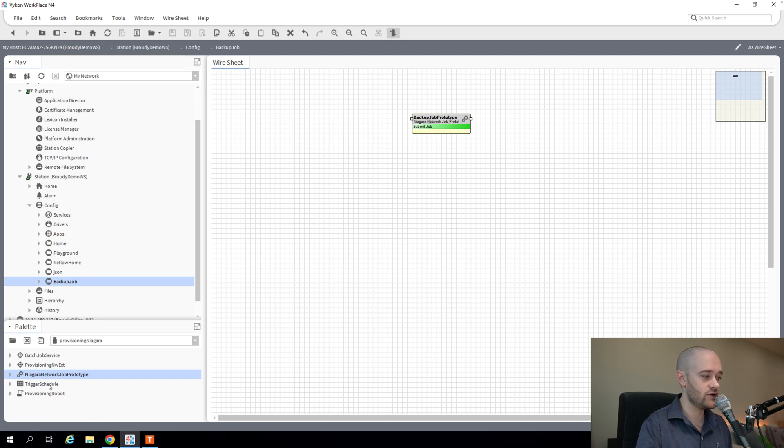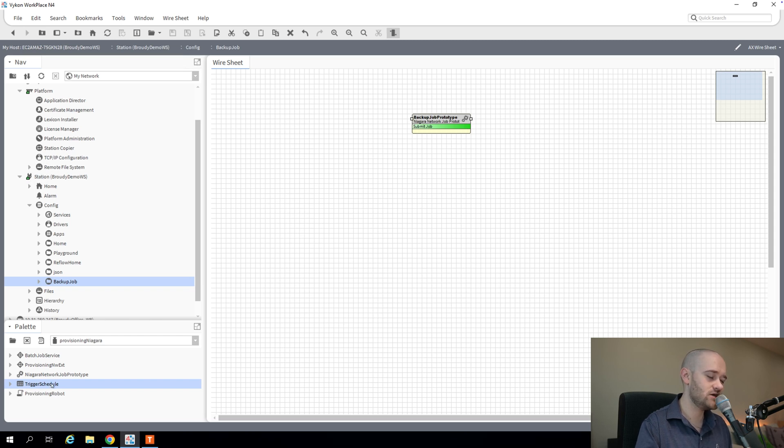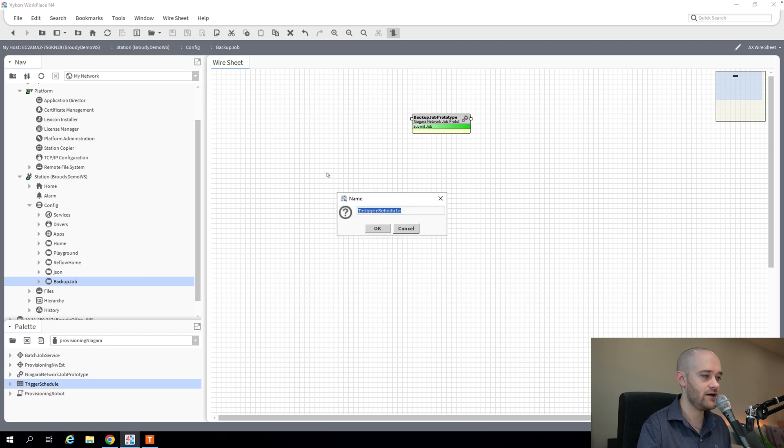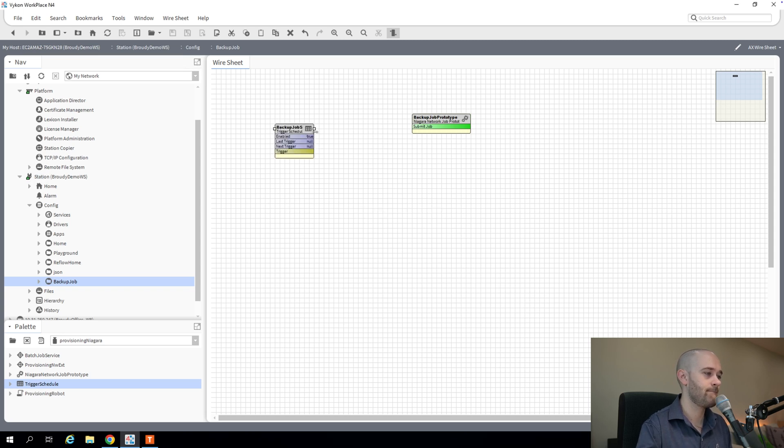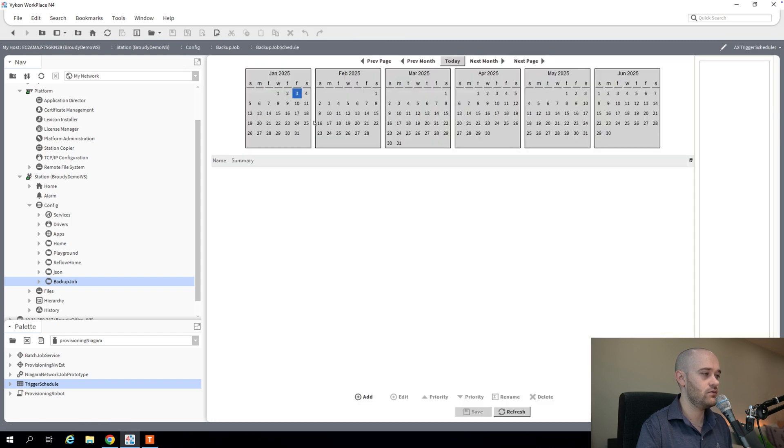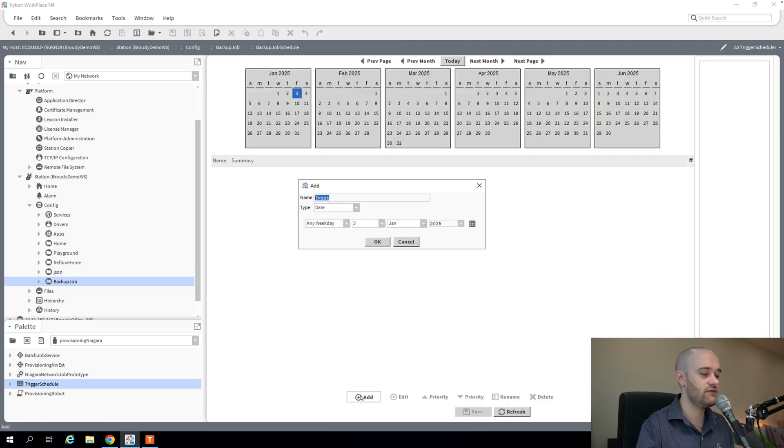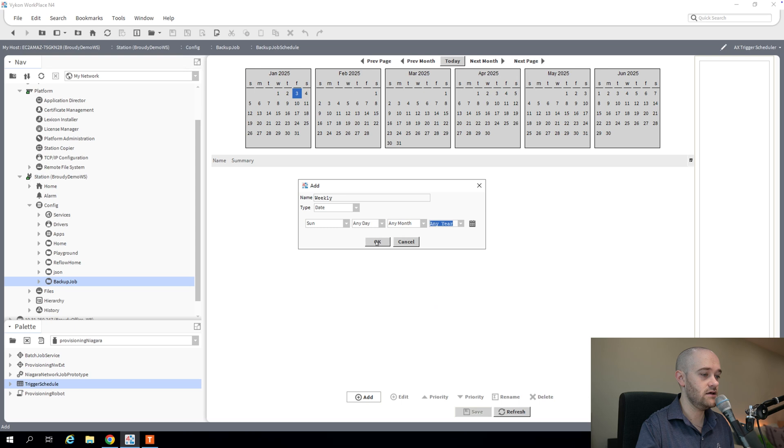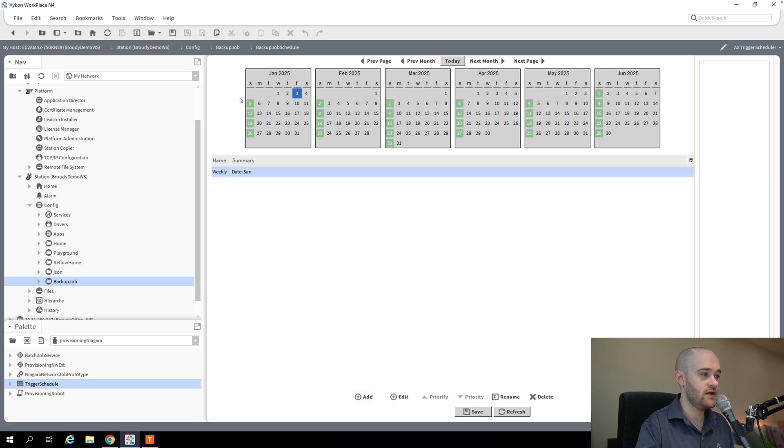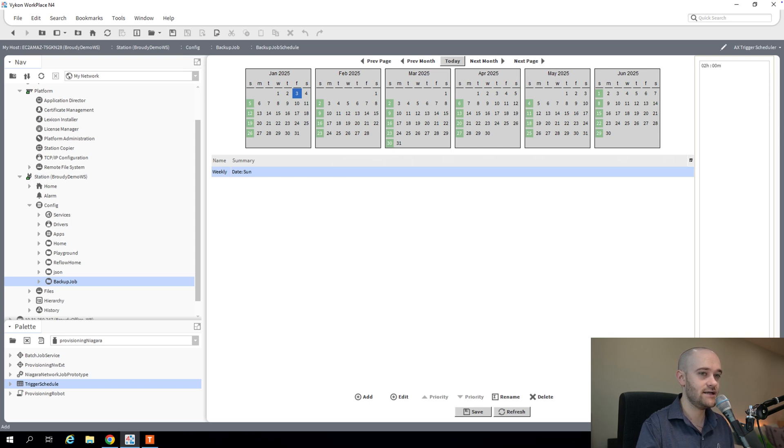And the way that we're going to do that is we're going to pull out a trigger schedule from the provisioning Niagara palette. But it is just a regular trigger schedule, so you could pull it from the schedule palette as well. But we'll call this backup job schedule. And then we'll go in here and we'll define how often we want this to happen. In my case, I'm going to say I want this weekly. And so I'm going to say every Sunday, any day, any month, any year. And we can see that's going to run every Sunday now. And then we also need to define a time. So over here on the right, we'll say like 2 a.m. Add in that time. Hit save.